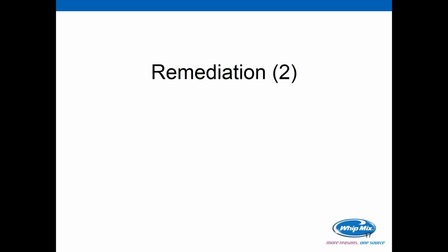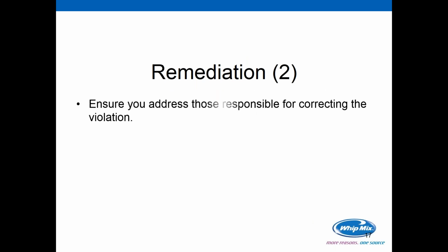Let's talk again some more about remediation. Ensure that you address those responsible for correcting the violation. Notice I did not say ensure you address those responsible for the problem. The FDA, from a regulatory standpoint, doesn't care what the source of the problem is. They only care that they have identified a problem, and it's up to you, the company, to put a fix in place to correct it.